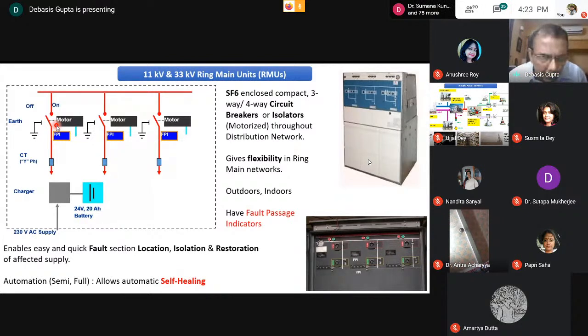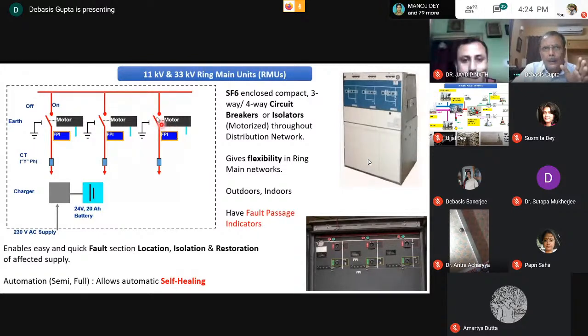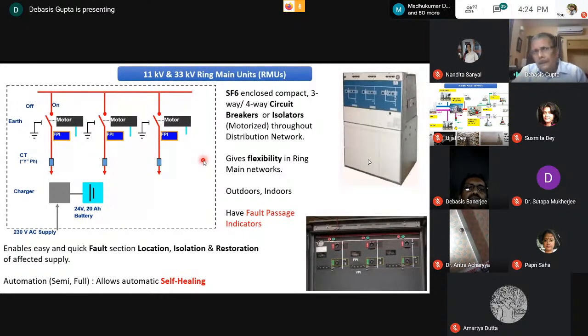Most cities in India use circuit breakers because they can place these RMU boxes inside buildings. In Calcutta, there's a dearth of space, so we had to place all this on the roads. Now, if you use a circuit breaker on the roads, you need very fragile protective relays, and with all the rain and moisture, that became a maintenance issue. So we decided to use a normal isolator instead, load break, fault make. You can easily break the load, and even if you switch back onto a fault, the upstream breaker will trip.